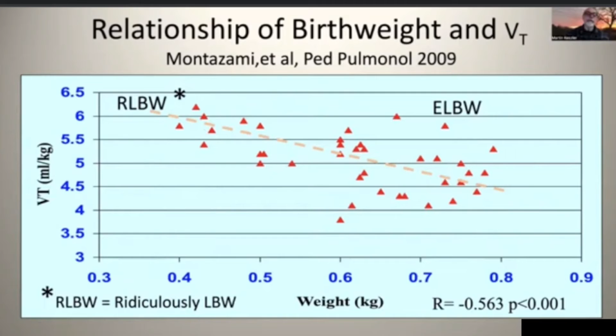And this has to do with the fact that the dead space of the flow sensor is fixed, and it's the same whether the baby is 800 grams or 400 grams, but it becomes proportionately larger, obviously, in the 400 gram baby, and therefore some compensation is needed, and tidal volume typically needs to be about 6 ml per kilo, not 4.5 or 5. Otherwise, we'll undersupport that baby.